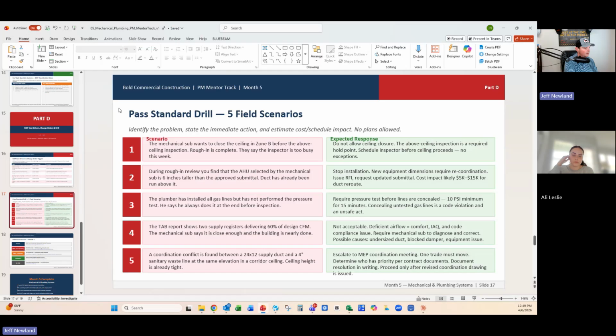So the TAB report shows 2 supply registers delivering 60% of the design CFM. The mechanical sub says it's close enough and the building is nearly done. Too bad. That's not going to fly. We need to figure out why. Oftentimes that's going to be because we have an air leak somewhere, or you're pumping too much air somewhere else. That's where you get your mechanical subcontractor on the phone, and y'all get it figured out with an on-site meeting most of the time.